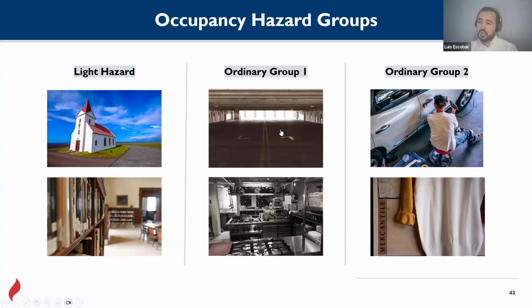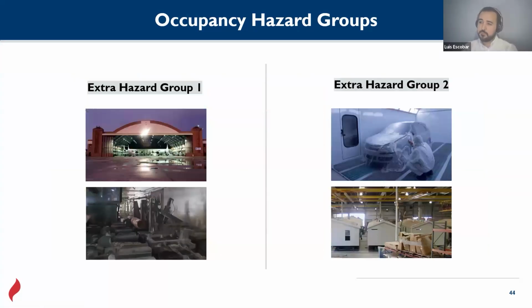Ordinary hazard group 1, parking lots and restaurants, for example. A little bit more heat release than light hazard, but not too high. Ordinary hazard group 2 is the design criteria we use most likely for mercantile occupancies, mechanical shops, and other applications where there's medium heat release. Extra hazard covers applications where we have combustibles that are dangerous, not for life itself, but if they catch fire, it's going to be hard to extinguish, and the heat release will be way higher than the previous ones we just saw.